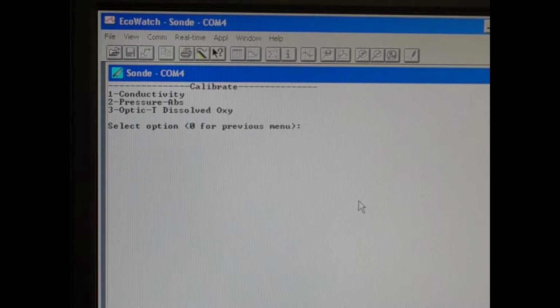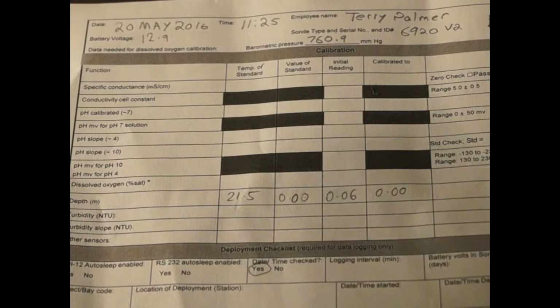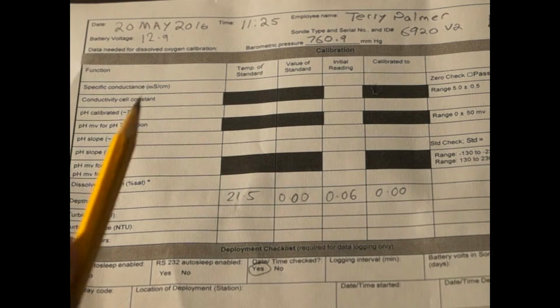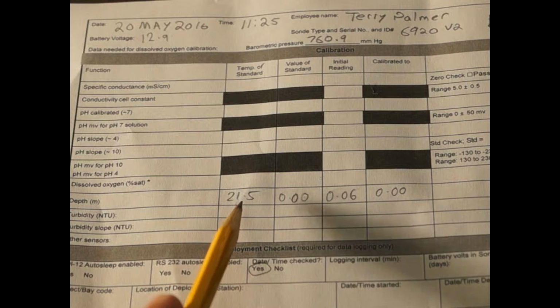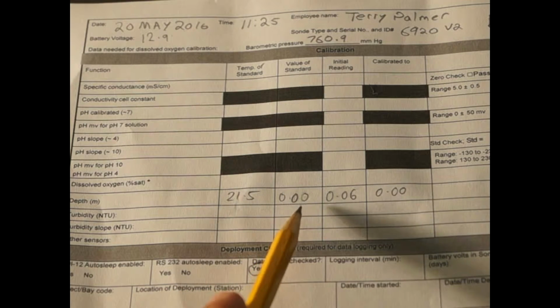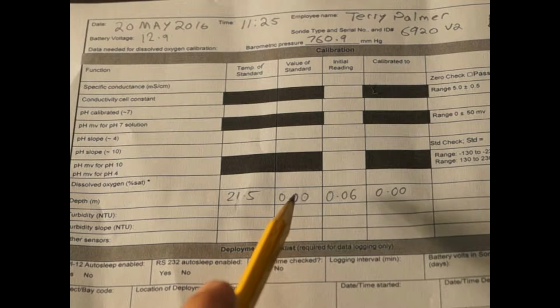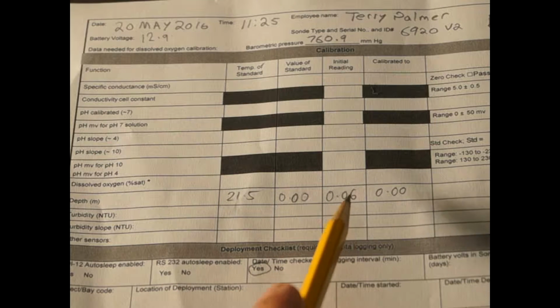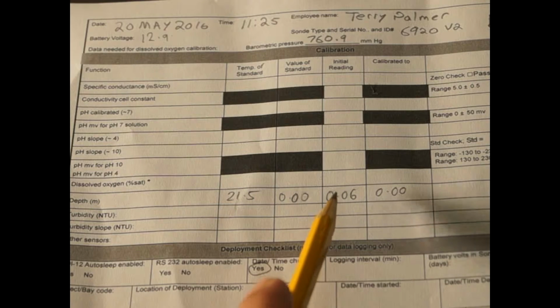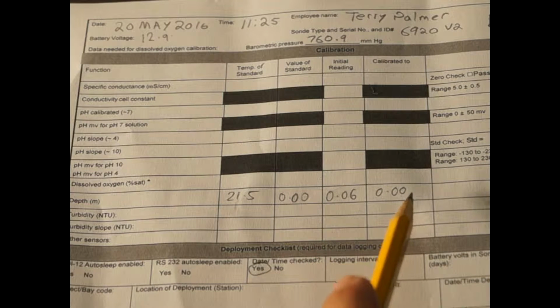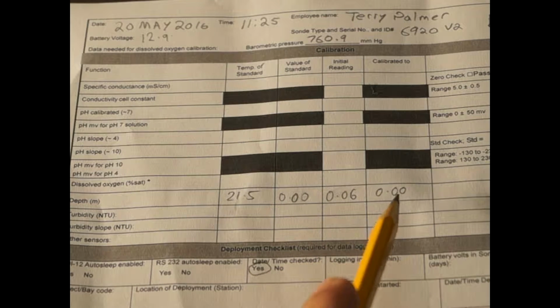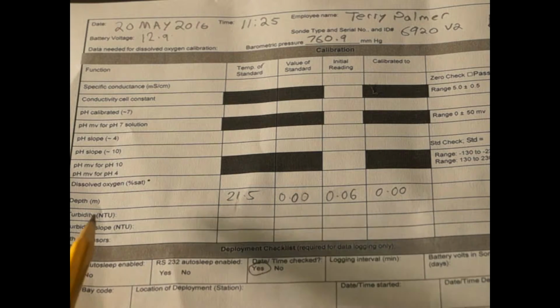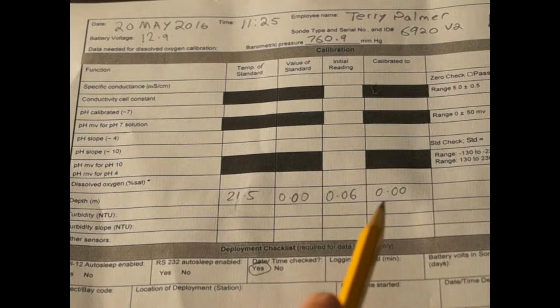So let's move to the calibration sheet. For the row that says depth, you write down the temperature that was on the probe, which was 21.5. Write down the value of the standard. The value is 0 because we're in the air, we have no depth. The initial reading was what it first came up on the display, and it was 0.06, so write down 0.06. And the calibrated to, that's after you push enter, and that's what the depth sensor now reads, which is 0. So now this is completed, so now we have completed the depth calibration for the Sonde unit.